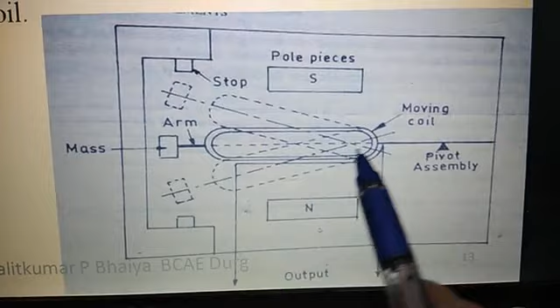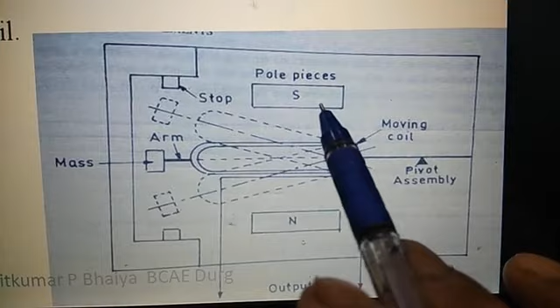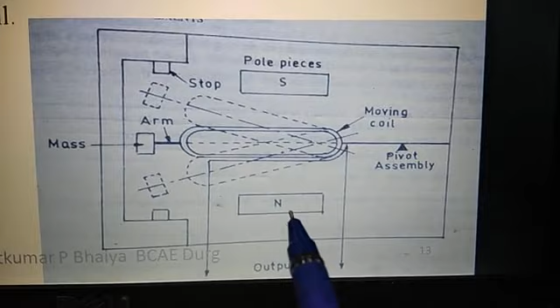This is the mass, this is the arm here, and this shows the moving coil, and this is the pivot assembly here, and this is the movement. So velocity will be measured due to this mass movement up and down, like a curved shape movement. And this is the pole piece of the magnet, south, and this is the pole piece of the magnet, north. As this movement occurs, the output is taken from the two ends of the coil. So the velocity of this mass will be in terms of the voltage available here. Voltage is generated in the coil which is proportional to the velocity of the coil.